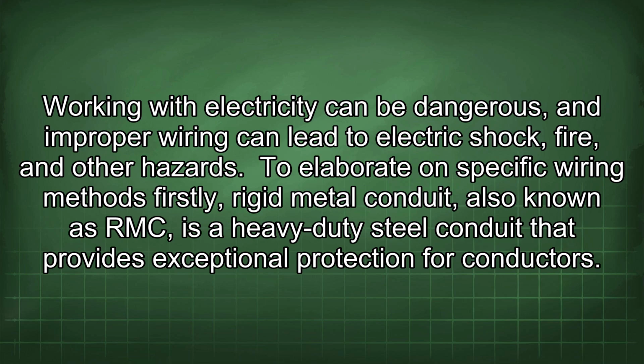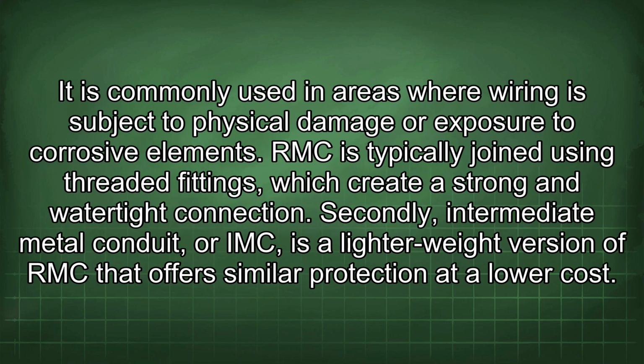To elaborate on specific wiring methods, firstly, rigid metal conduit, also known as RMC, is a heavy-duty steel conduit that provides exceptional protection for conductors. It is commonly used in areas where wiring is subject to physical damage or exposure to corrosive elements. RMC is typically joined using threaded fittings, which create a strong and watertight connection. Secondly, intermediate metal conduit, or IMC, is a lighter weight version of RMC that offers similar protection at a lower cost.